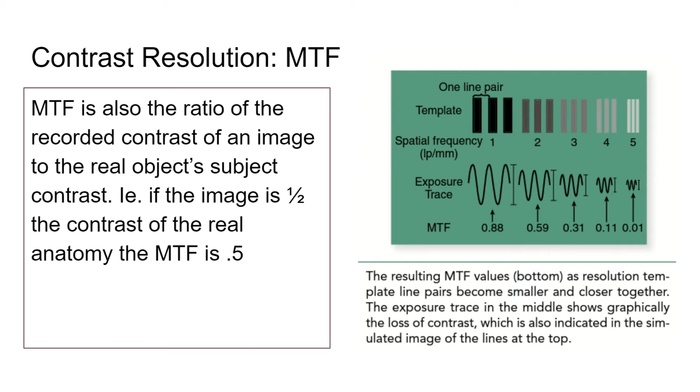Here's another way of looking at it, right? We say that MTF is really the comparison of the contrast that's in the image versus the contrast of the actual object if you were to rip it out of the patient and look at it.